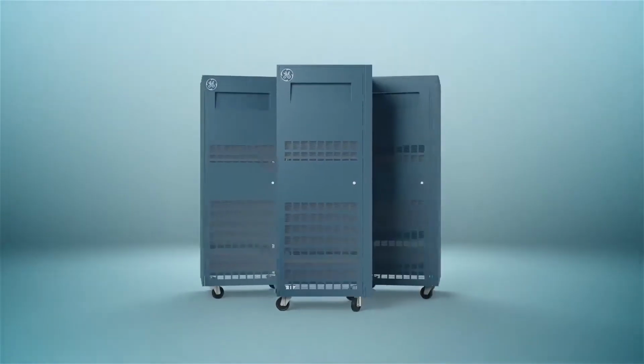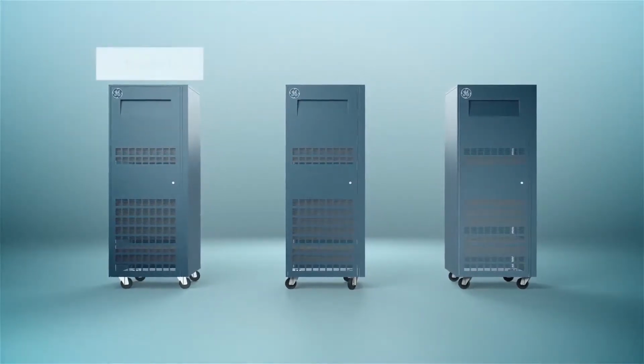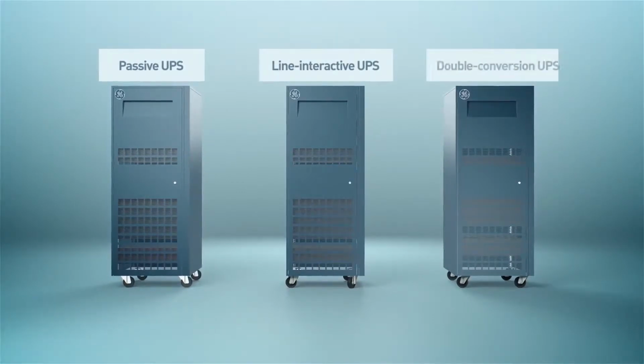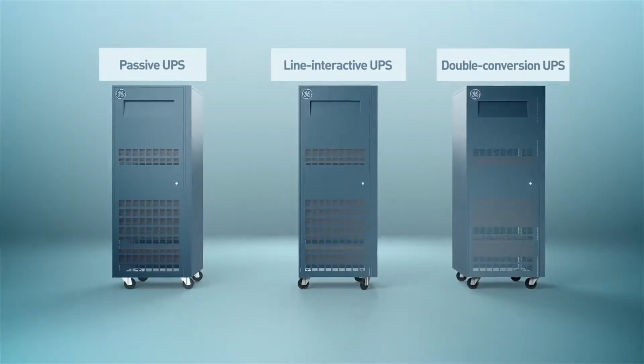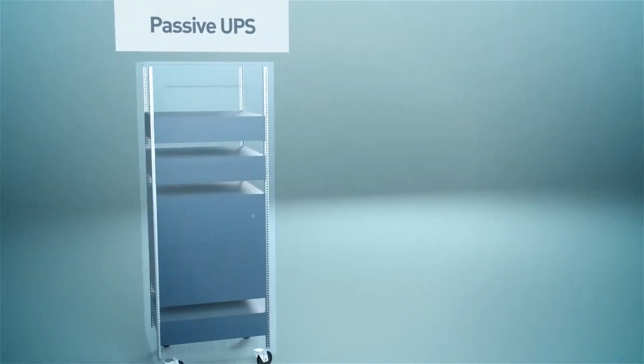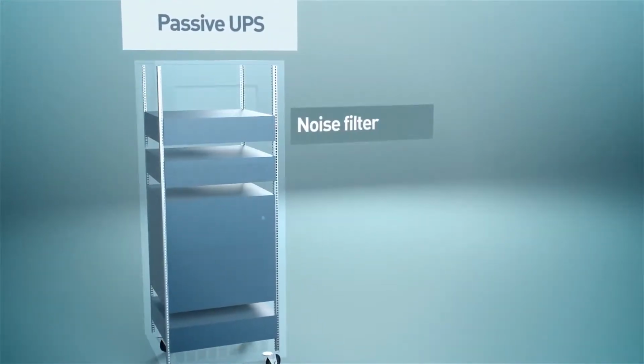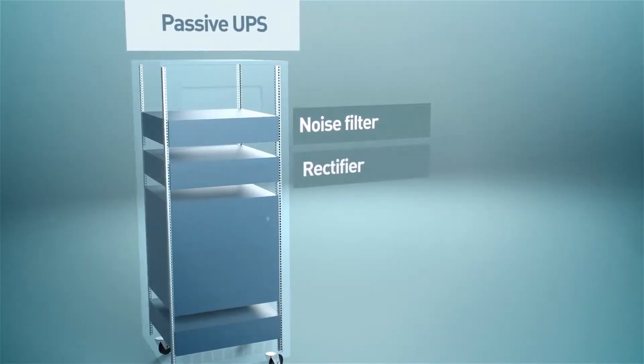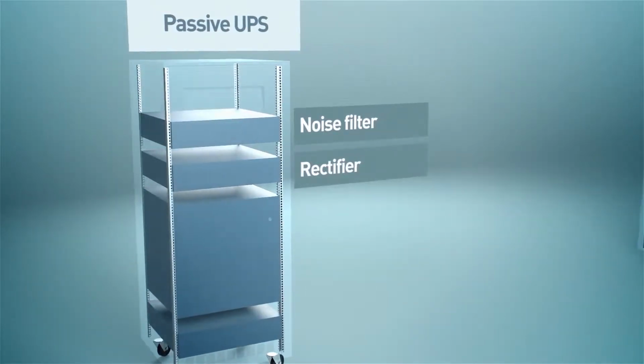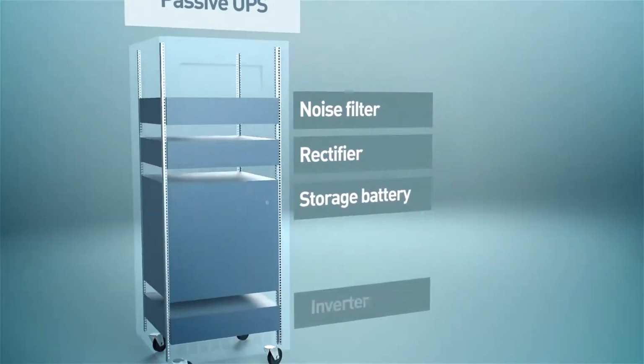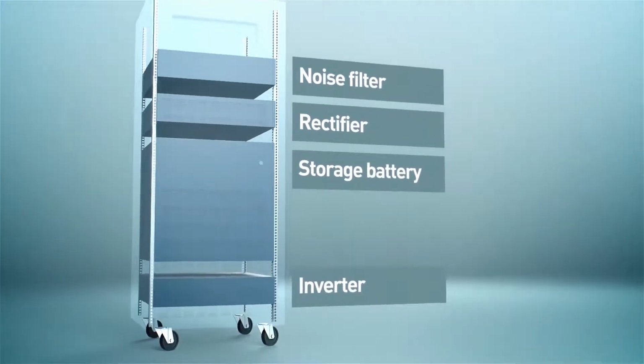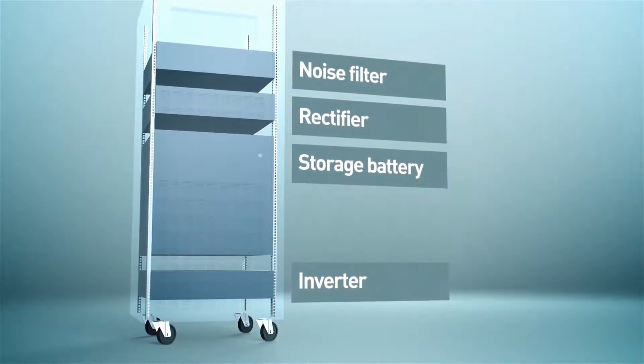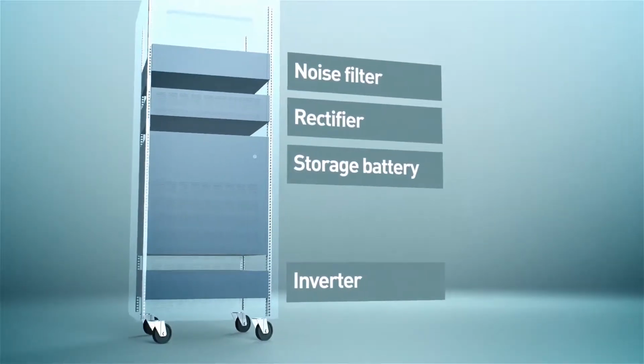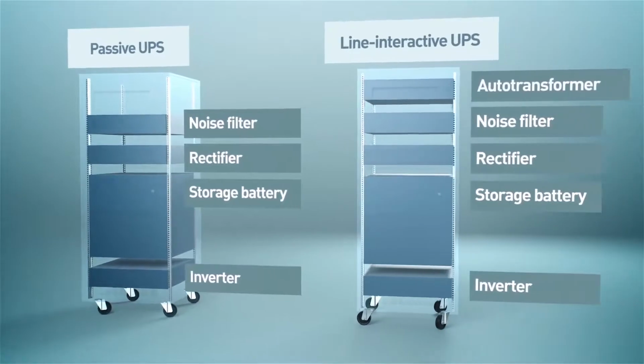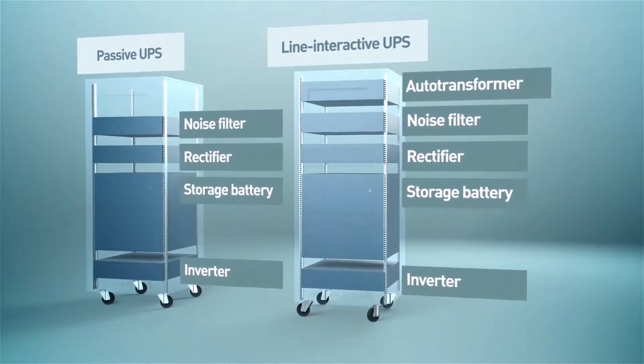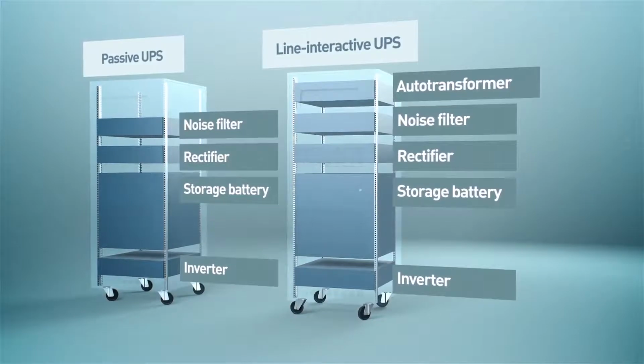All UPS models can be divided into three large groups: passive, line interactive and double conversion UPS. Passive type UPS models are the simplest devices. They consist of a filter, which reduces the noise of the input voltage. A rectifier converts AC power to DC power to charge the battery, while an inverter converts the DC back to AC to feed the load if electricity fails. Line interactive devices also have an auto transformer, which eliminates voltage surges without switching the device to offline operation mode.